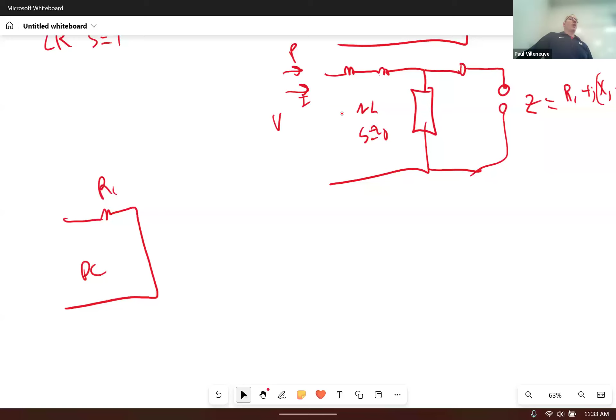And then the DC test, everything's shorted out. Under DC conditions, we only have R1. Now that's when you've got to look at it and see if it's configured in Y or delta, but all you have is R1. Why? Because this is an inductor over here, and what happens to an inductor in DC? It shorts out. So there's no current going into the rotor circuit under DC conditions - just a short circuit.